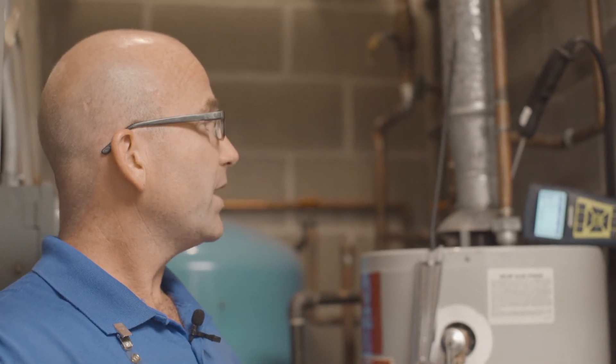So if I saw too high of a number on my combustion analyzer, like on a furnace, I will immediately stop what I'm doing and I'll start investigating the reason for that.